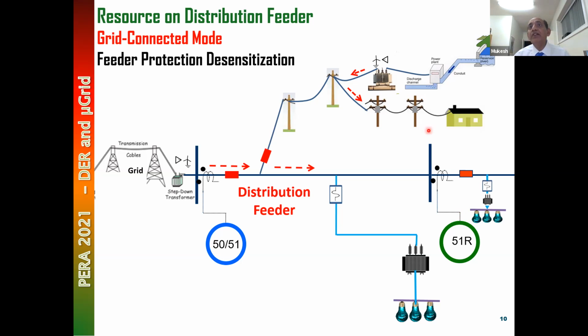Now let's say we connected a run-of-the-river plant to this distribution feeder. So the run-of-the-river plant is here. Again, it will be connected to a transformer. The power may be generated at 400 volts, lifted up to the 25 kV feeder voltage.